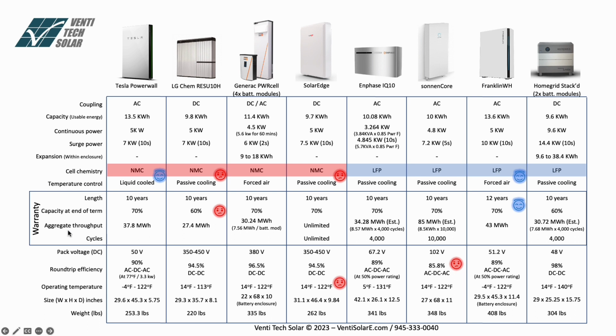Now let's talk about aggregate throughput. Aggregate throughput is how much energy you're supposed to get out of the storage system after 10 years if you use it within the parameters of the warranty. So 10 years charging and discharging 13.5 kilowatt hours gives you 37.8 megawatt hours. If you discharge 9.8 kilowatt hours for 10 years and expect to have 60% of the battery, you will get 27.4 megawatt hours at the end of 10 years. And these are parameters that are stated in the warranty.